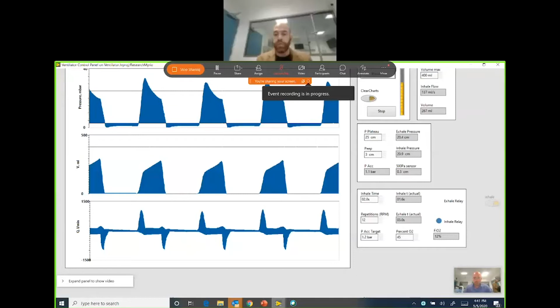This is very important. A lot of designs, even the Imperial College design, which was lauded as a very good design, were using only one limb. So the pressure sensor and the flow sensor are only on the inhale, and in our opinion, this is very dangerous, because one of the important parts of safety is actually measuring the inhale versus exhale. So if we have a leakage, if there is some reason that some leakage is inside or outside the patient, we'll be able to detect it.